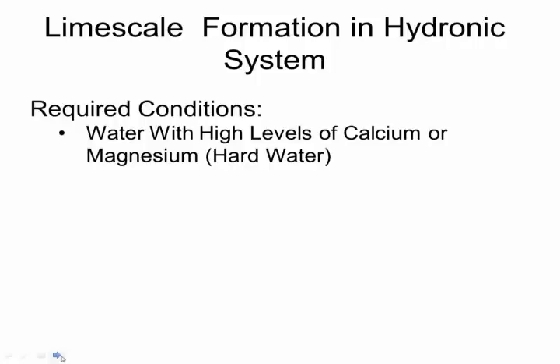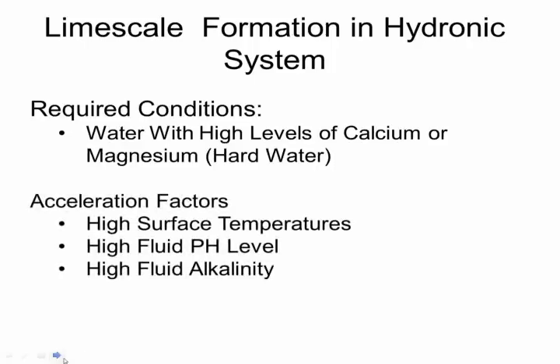Well, the required condition in a system is that you'd have to have levels of calcium or magnesium in your system, hard water. If you don't have calcium or magnesium, you don't have to be worried so much about limescale buildup. And an acceleration factor that could cause limescale to form fairly quickly is if your surface temperature is high. As an example, in a domestic hot water system, you could end up with your hot water heater heat exchanger failing because of scale buildup, and then 3 feet away from the hot water heater, you can cut your copper pipes and look at them, and they'll be perfectly clean because they're relatively cool. So surface temperature has a lot to do with acceleration factors.